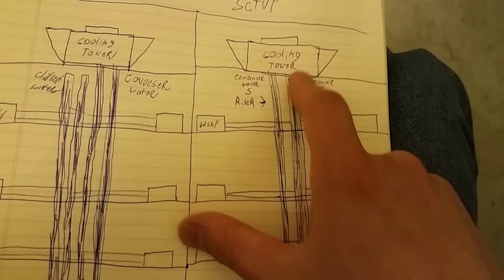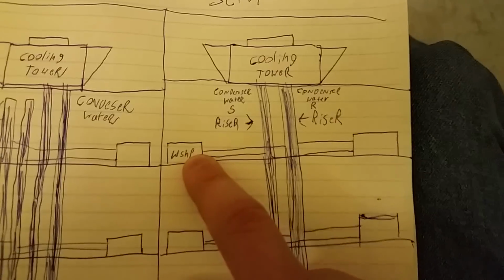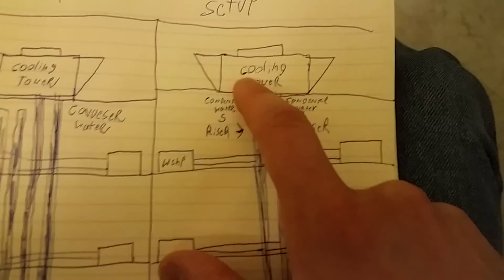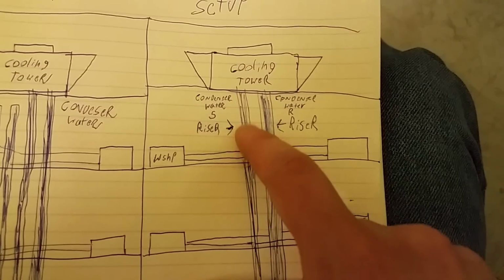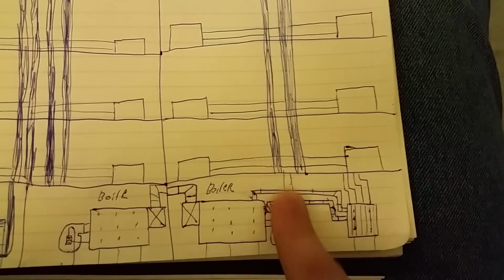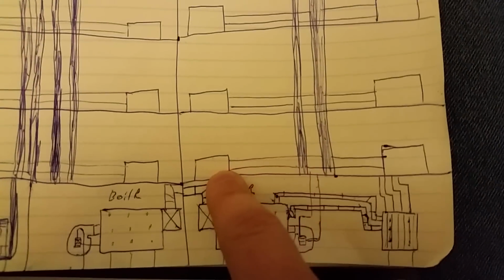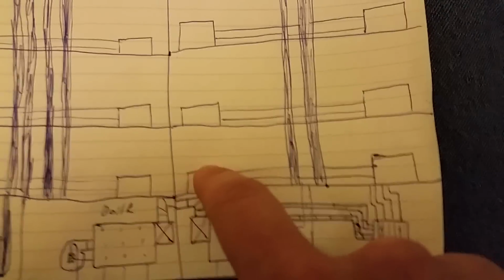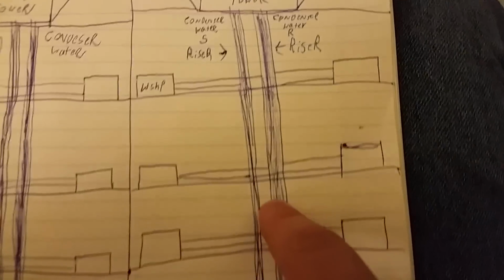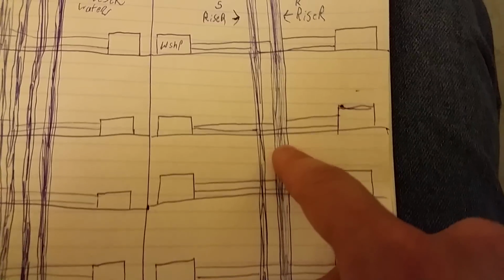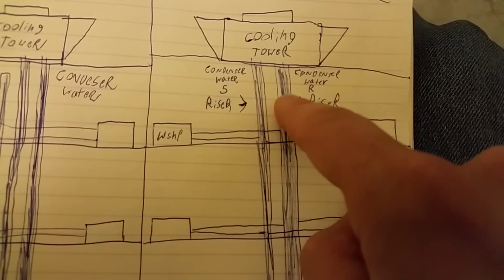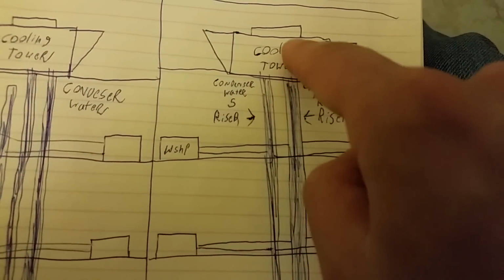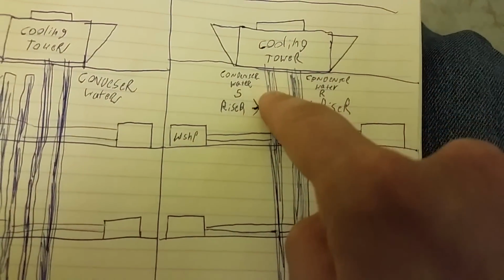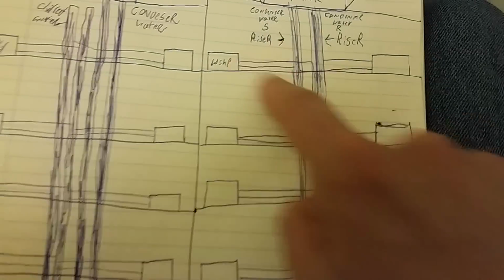They're cooled by the condenser water. So all these compressors are cooled by condenser water, and it's cooled by the tower. Water comes up. Here's your supply water. So supply water, we'll start from the bottom. Supply water comes up, goes in, cools a little heat exchanger in there for the compressor, goes up to the return. That return is going to the tower to be cooled, and then comes back down to the supply and goes back into these units and recirculates again.